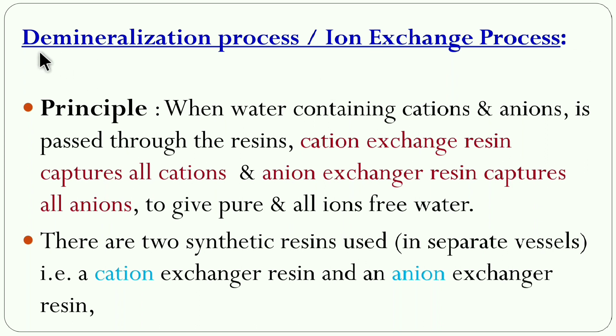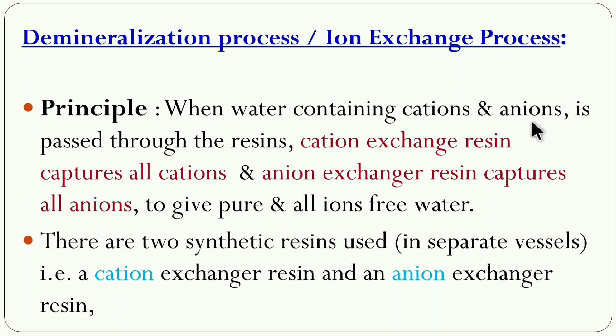The name itself — demineralization — 'de' means loss and 'mineral' refers to ions, so there is a loss of all ions present in the water. In ion exchange, only H⁺ and OH⁻ ions are exchanged. The principle is: when water containing cations, anions, or ionic impurities is passed through resins — a cation exchanger resin and an anion exchanger resin — the cation exchanger captures all cations and the anion exchanger captures all anions, making the water free from all ionic impurities. Two types of resins are used in separate vessels.